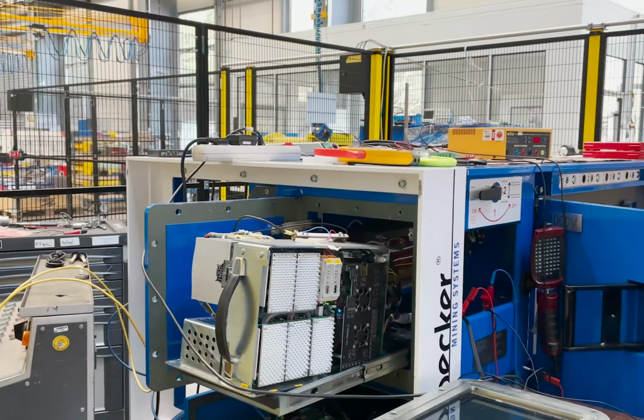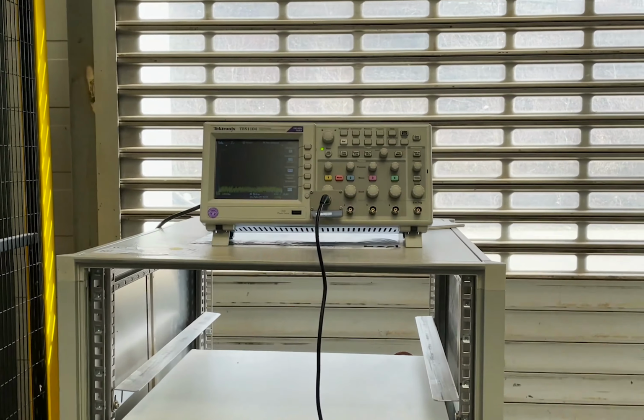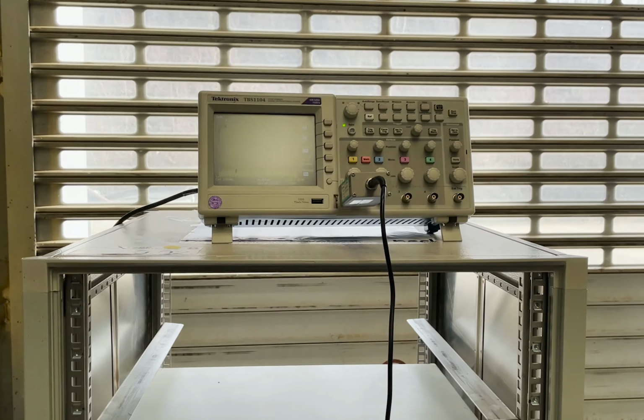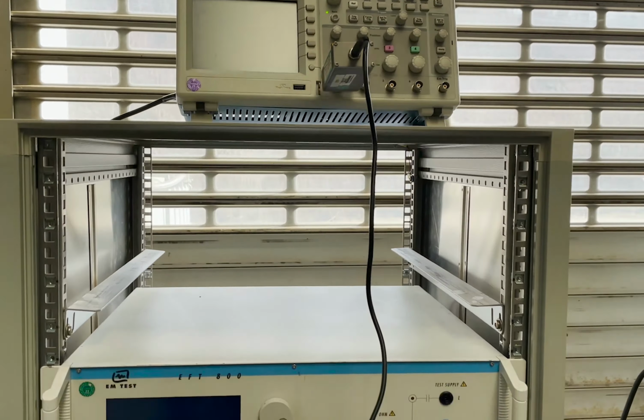A 1 kV 400 kW motor and a 250 kW brake is used for the real switching tests of the contactors. High voltage and high current functionality tests such as the current measurement, voltage measurement, short circuit tripping, voltage tripping, high voltage isolation test, and loss of vacuum are tested in this facility. This part of our warehouse stores our inventory for transformer, substations, and switchgears before delivery or integration into flame-proof tanks.